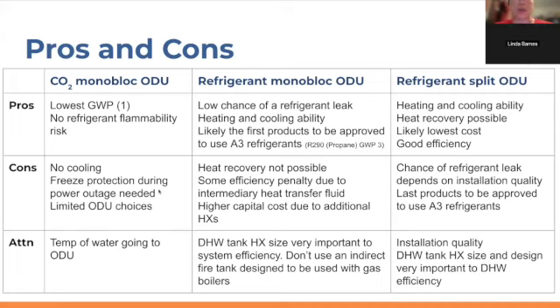So, in the refrigerant monoblock outdoor unit type of equipment, you need to work with your contractor and emphasize to the contractor that it's very important that the domestic hot water tank heat exchanger is large. Do not buy an indirect fire water heater tank that's designed to be used with a gas boiler and hook it up to a heat pump that has a refrigerant monoblock outdoor unit style heat pump. It just will not work well because a gas boiler can generate 190 or 180 degree Fahrenheit water, and refrigerant monoblock outdoor units cannot do that.